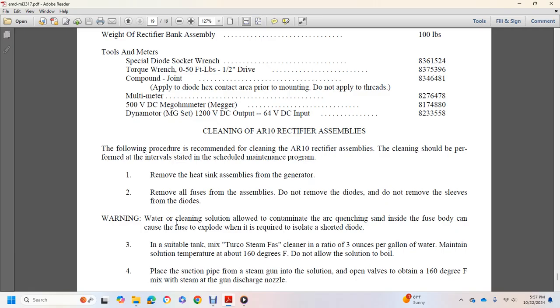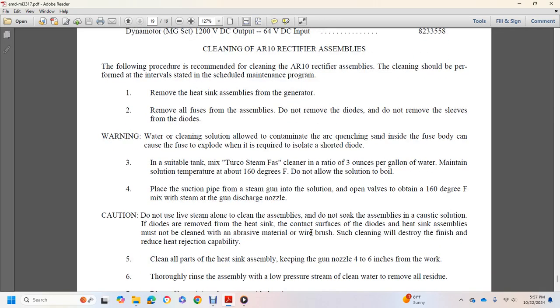1. Remove the heat sink assembly of the generator. 2. Remove the assembly. Do not remove the diode. Do not remove the sleeve from the diodes. Warning: water cleaning solution allowed to contaminate the arc quenching sand inside of the fuse body can cause the fuse to explode when required to isolate a shorted diode. 3. Install in a suitable tank a mixture of Turco Steam Fas cleaner in the ratio of 3 ounces per gallon of water. Maintain the solution temperature at 160 degrees Fahrenheit. Do not allow the solution to boil.